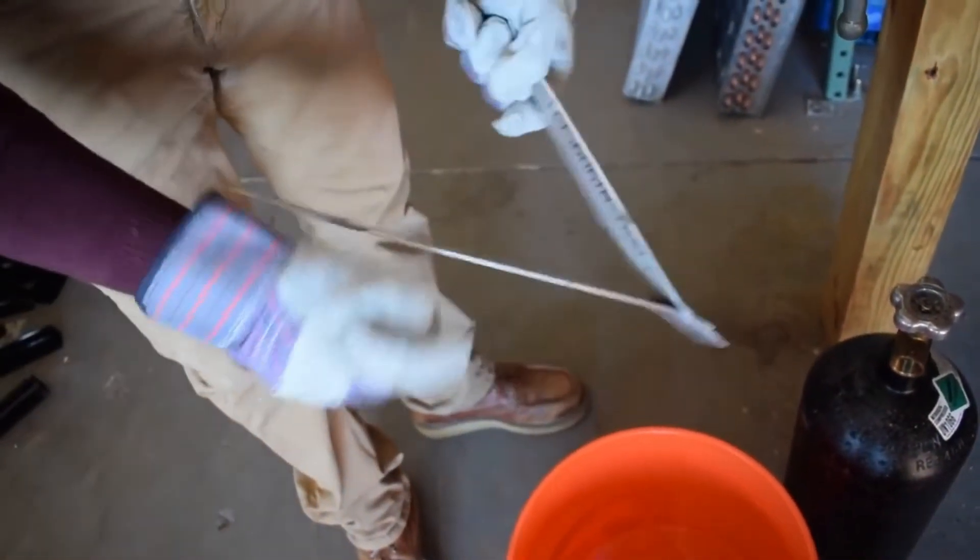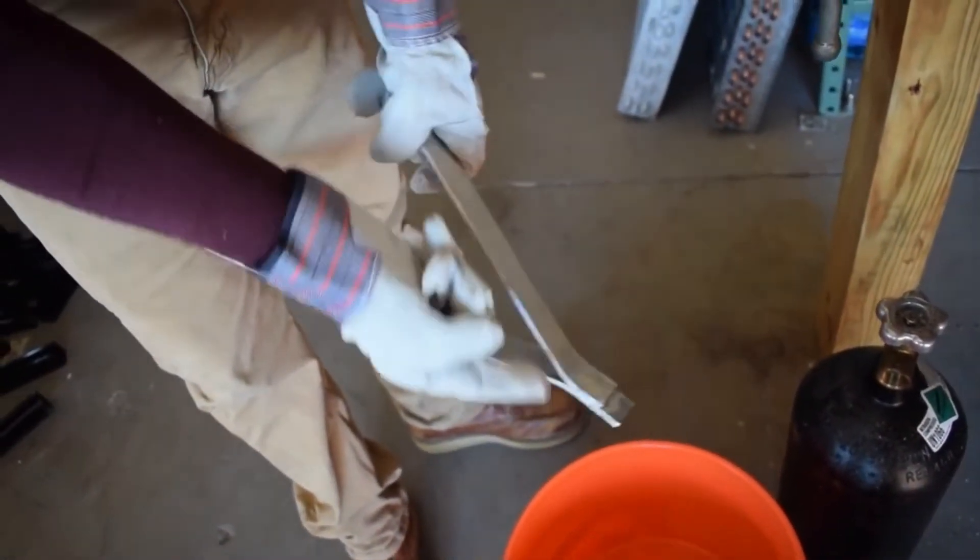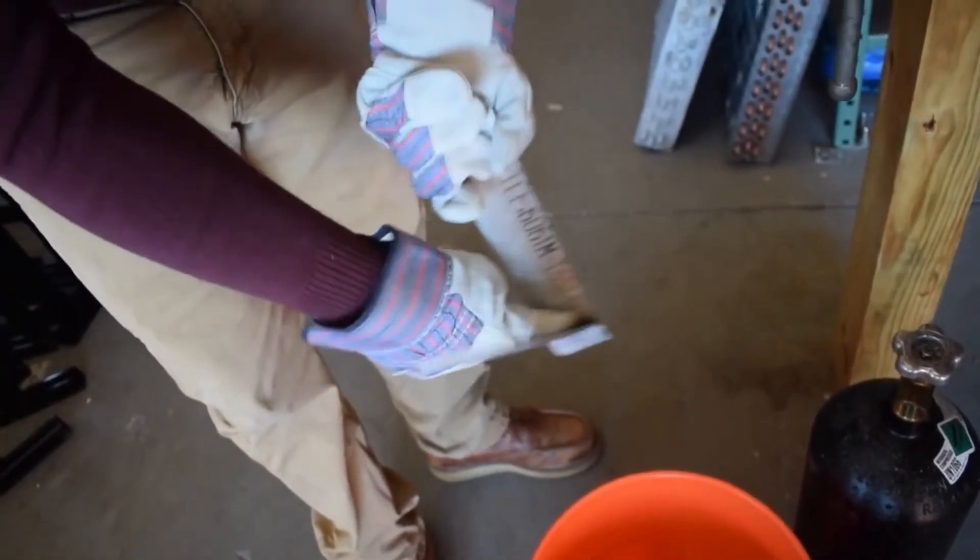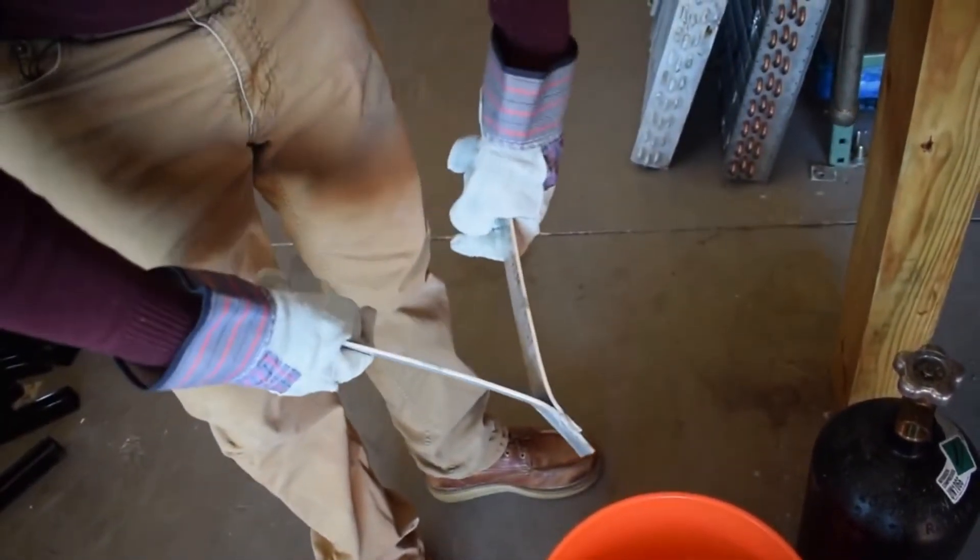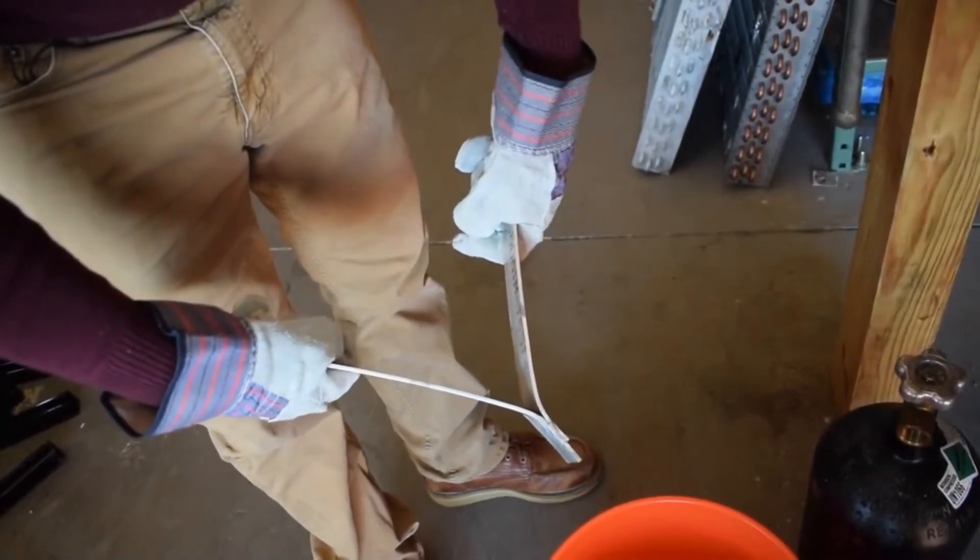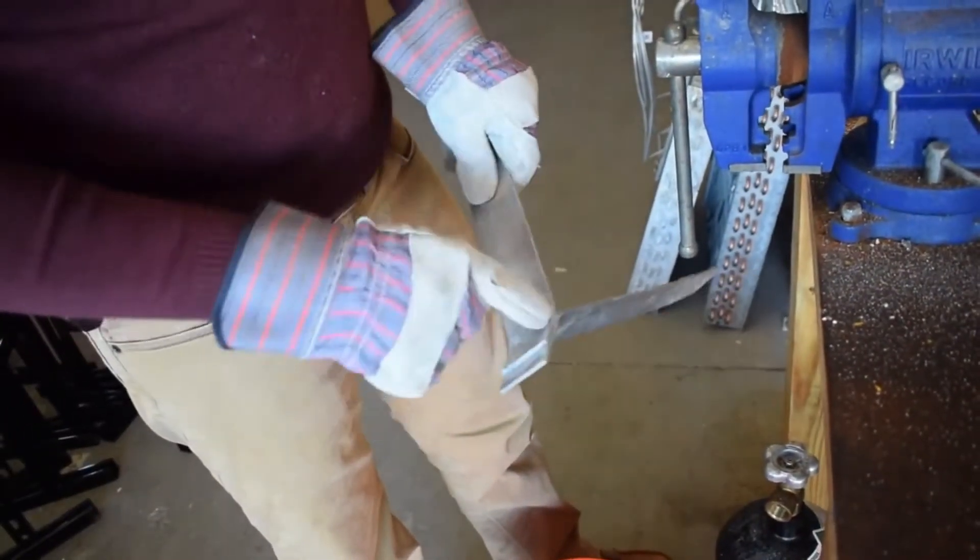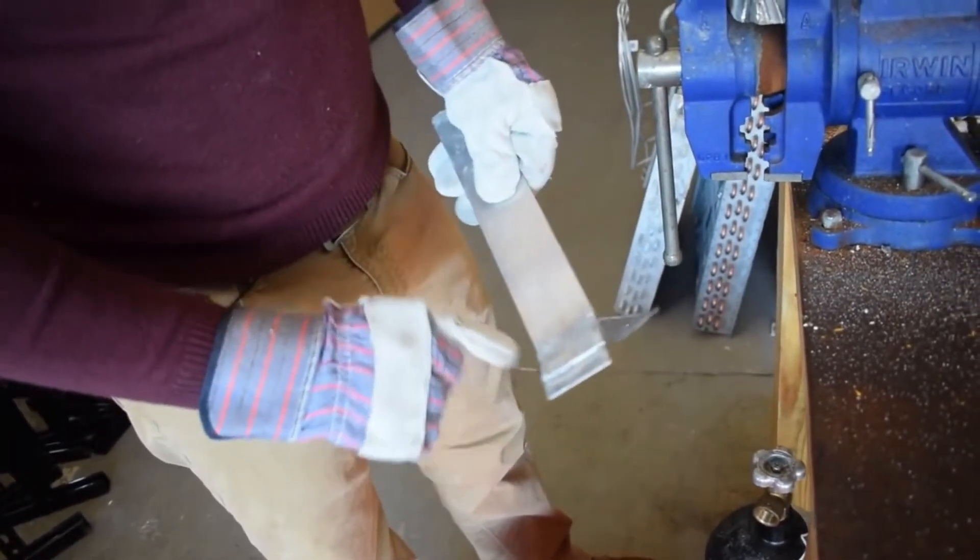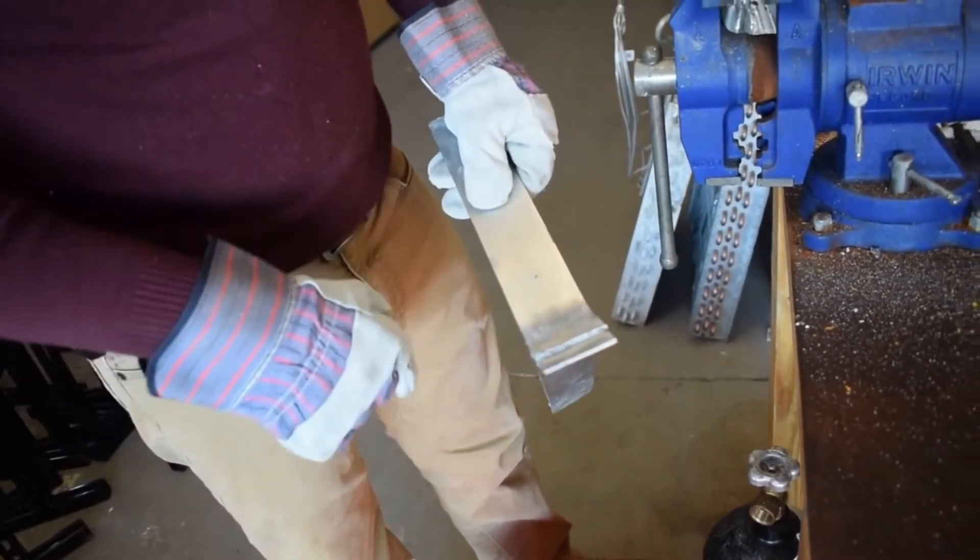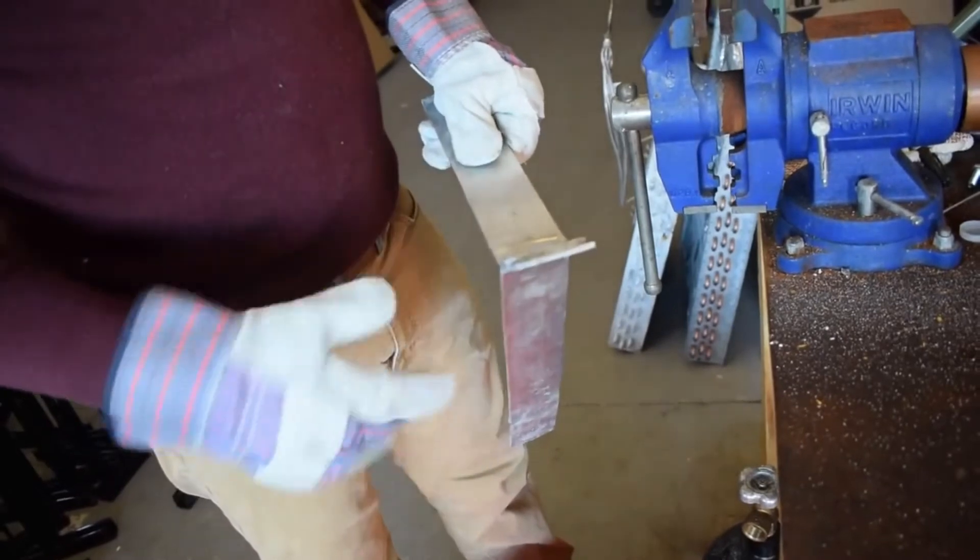You can see that even though with this product I don't pull as much into the joint, it's not like I've pulled a lot of solder in. Just the butt connection on that solder is extremely strong with the alloy braze. And again, I would use this specifically when you're working with thicker plate aluminum, not necessarily when patching a coil. For that application, I would definitely use alloy saw.